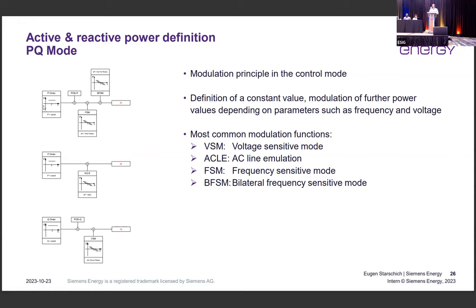For example, it can be used for power oscillation damping. If I see a certain phase difference or a frequency difference, then based on this difference in the frequency, I can add or subtract power depending on the difference. This is what we call a modulation. That gives a lot of flexibility in terms of the control. The operator does not need to select whether they want active power control or an AC line emulation. As shown here, you can have both.